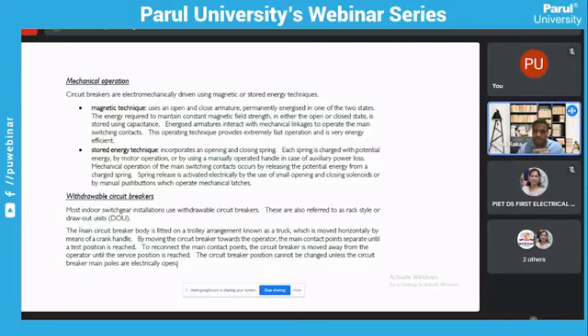Now, coming to the next point, withdrawable circuit breakers. Most Indoor switchgear installations use withdrawable circuit breakers. But talking about industry practices, especially those followed in the UK, or maybe nowadays in India as well, a lot of state utility companies as well as national utility companies are shifting from AIS to gas insulated switchgear, considering that they can accommodate more feeders and more panels, and achieve the same feeder count while deploying versus air insulated withdrawable circuit breakers. So that is another point.